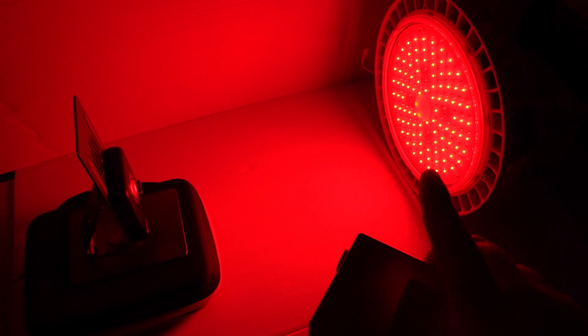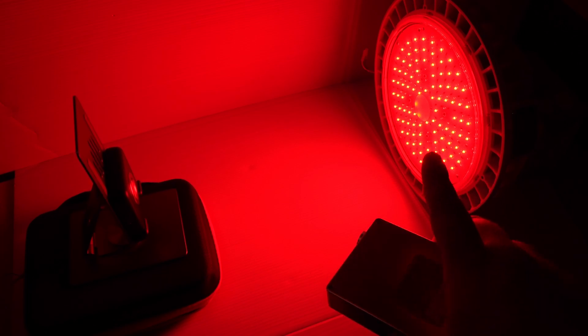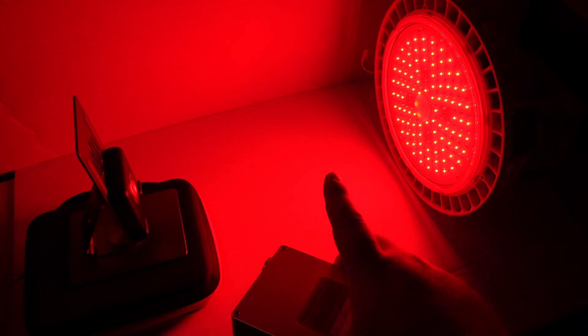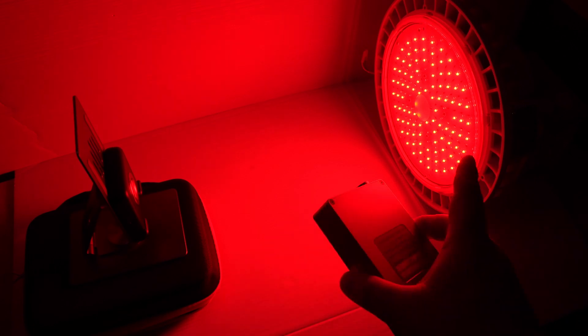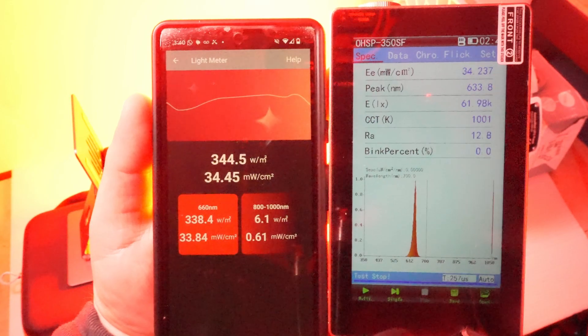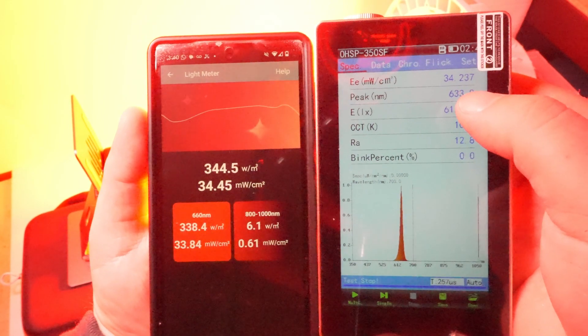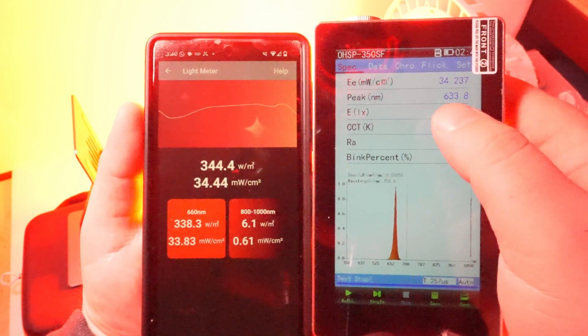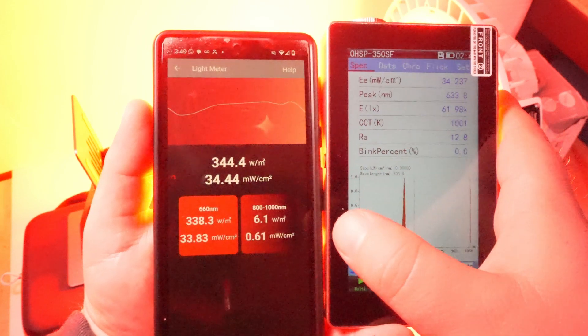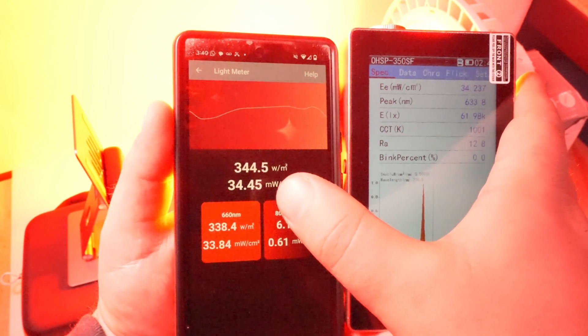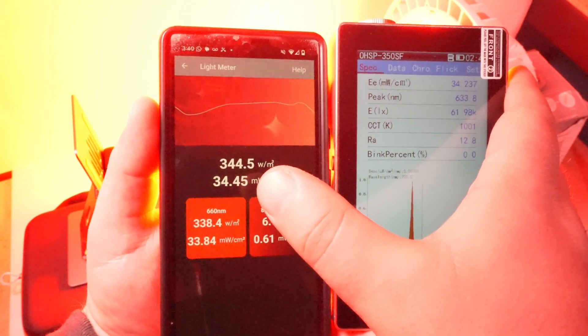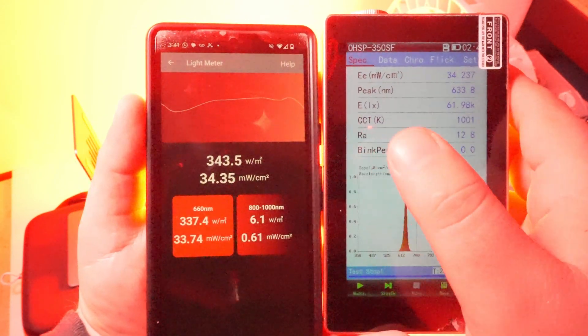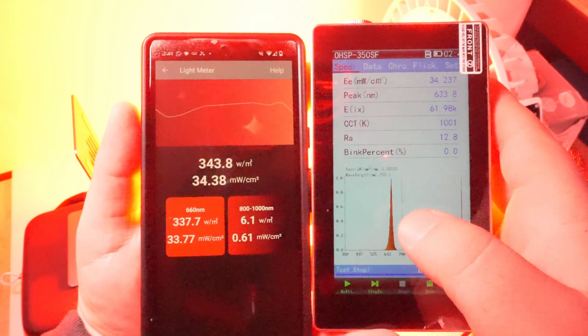Now I have another UFO light, except this one is all 630 nanometers. We can just check how accurate it is with the 630 wavelength. Just adjusted the contrast. You can see we get 34 milliwatts per centimeter squared with the 633 nanometer wavelength, and on the Viver sensor we're getting 34 milliwatts per centimeter squared. Matches up very well, actually surprisingly well.